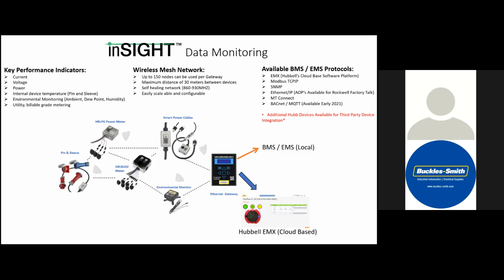Now that leads to all these devices taking the information and bringing that information back into the gateway. That type of information they're going to get, which we call our key performance indicators. They're going to get any type of currents, voltage, power. On the pin and sleeve, they'll actually get device temperature at the connection point for each phase. And then we have our environmental monitors that do ambient, dew point, and humidity. And all of these are over 99% accurate and utility billable grade for anybody who's using, let's say, a colo location or any type of sub-metering for some reason or another.